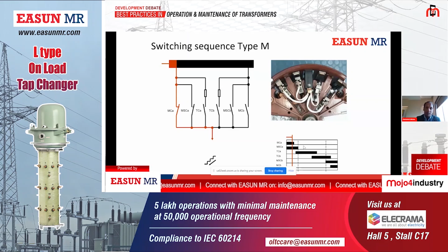While it is operating, the tap changer principle is very simple: make before break. Whatever tap changer you have, while you are going to the next step, you have to make that connection, and only then break in the winding. Otherwise, the transformer will fail. To overcome that discontinuity, we use transition resistance. How does transition resistance come into the picture? We are creating a circulating current. You can see in the circuit, it is explained very nicely.